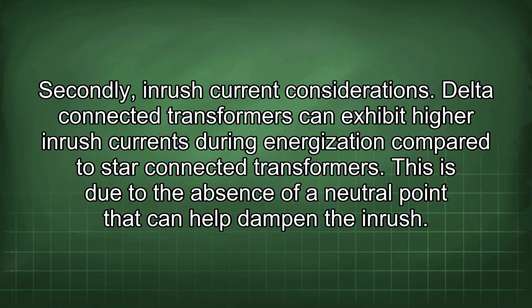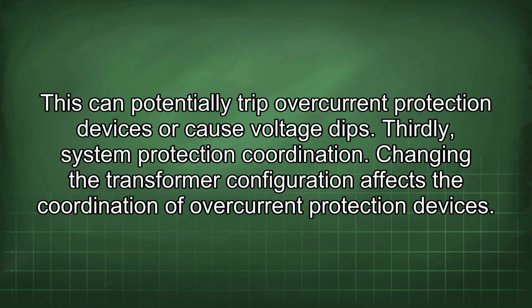Secondly, inrush current considerations. Delta-connected transformers can exhibit higher inrush currents during energization compared to star-connected transformers. This is due to the absence of a neutral point that can help dampen the inrush. This can potentially trip overcurrent protection devices or cause voltage dips.